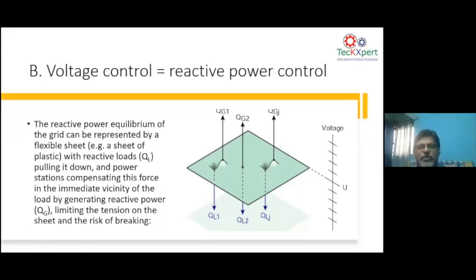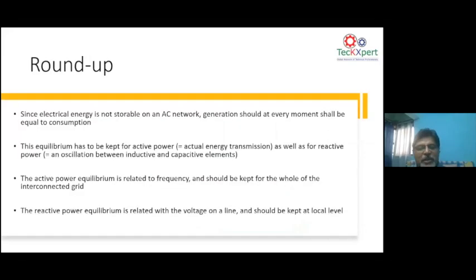Sometimes reactive power control can be done locally. The ultimate objective of reactive power correction is to pump in reactive power by capacitor banks, or we can use a static compensation system like static VAR or STATCOM systems. That is how we control the voltage. So on one side, for active power, we maintain the frequency by generating power equal to the demand, and the equilibrium of the power has to be kept by maintaining the frequency. And when it comes to reactive power, we have to ensure that the required amount of reactive power is pumped in, so that the voltage is also kept in equilibrium.